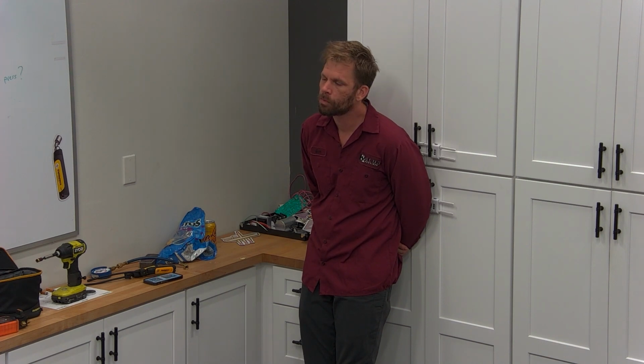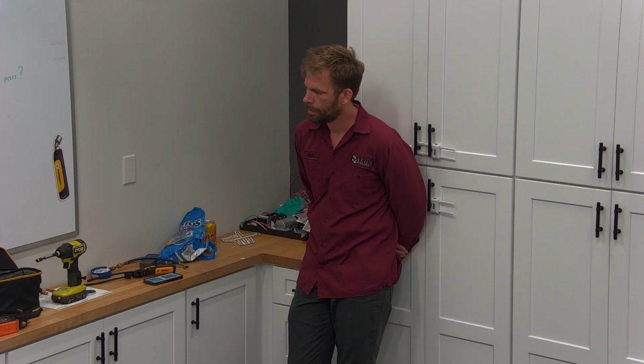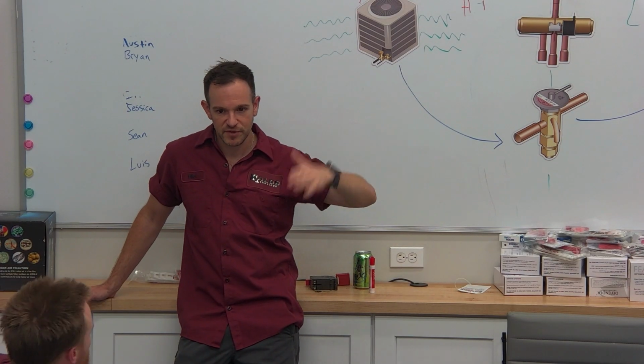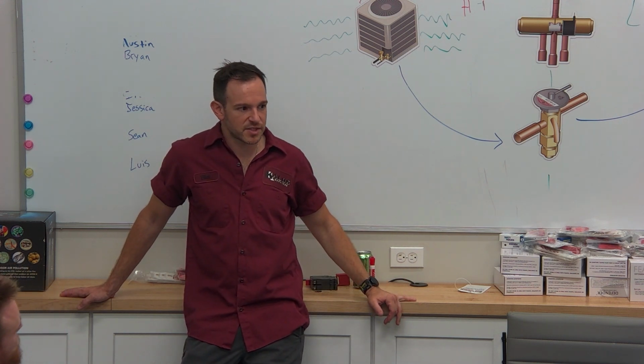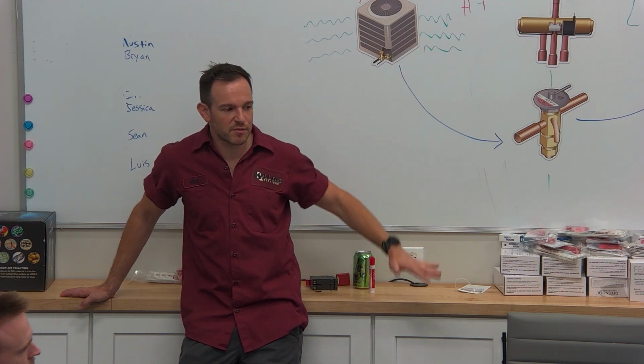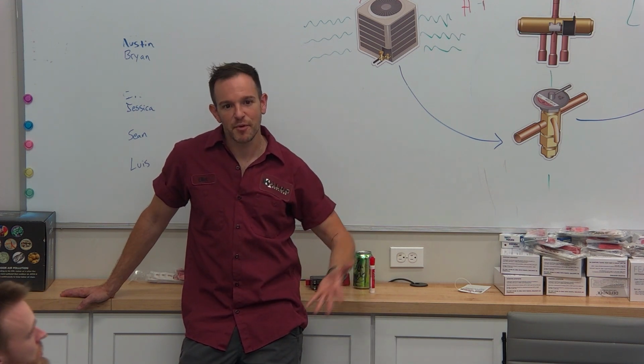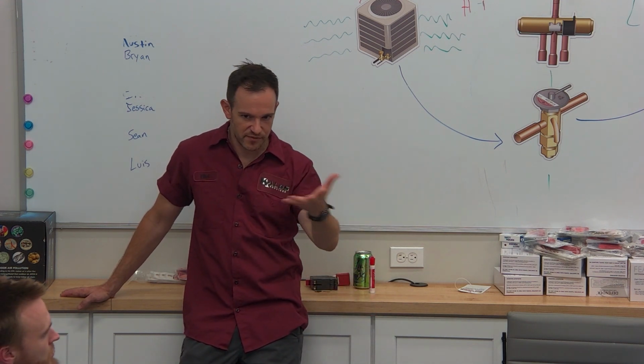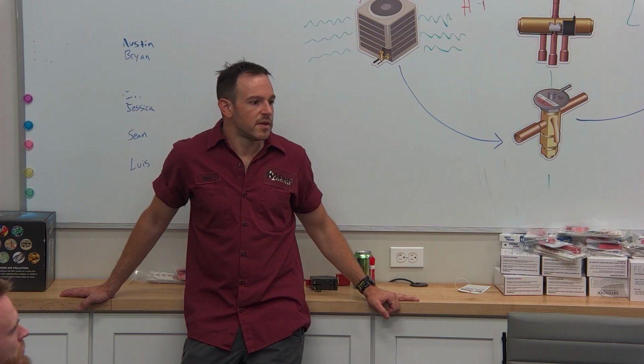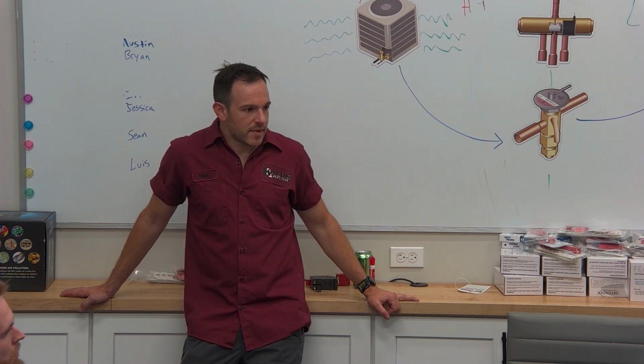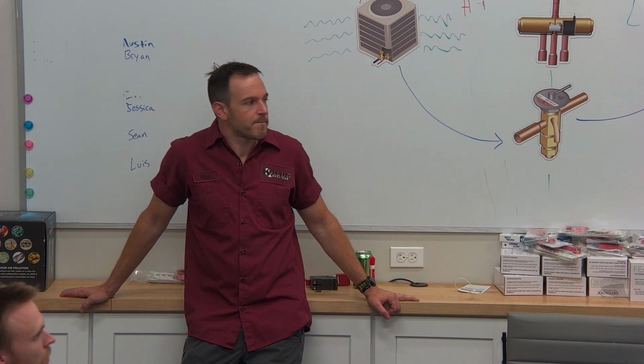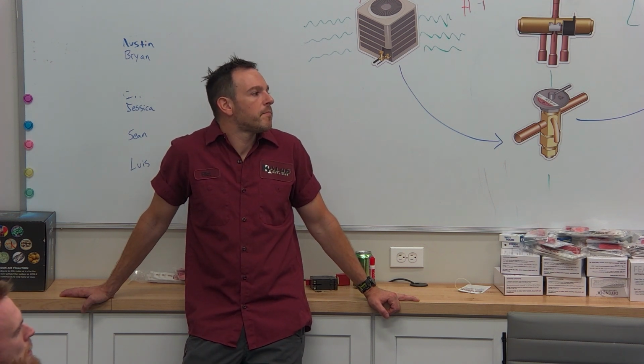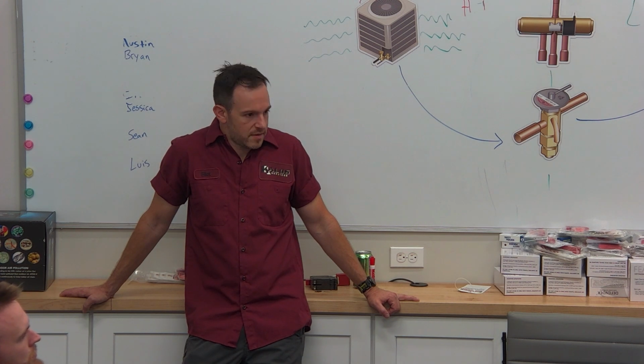I was gonna say real quick, low is relative, some of that's gonna come with experience, but this is where we use that rule of thumb, where we're taking our return air temperature and we're checking to see, are we 35 degrees below on our saturation? So anything that's below that is what we mean by low, because just because the number itself is low doesn't mean you have a problem if you're working with a different kind of refrigerant. That's if it's cold in that room already. It's cold, yeah. Dirty filter. Dirty filter, okay. I'm not gonna write dirty filter because we want a more broad description in that third, but the dirty filter is one of the parts of that.